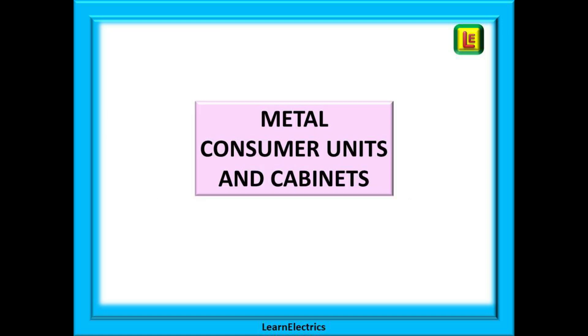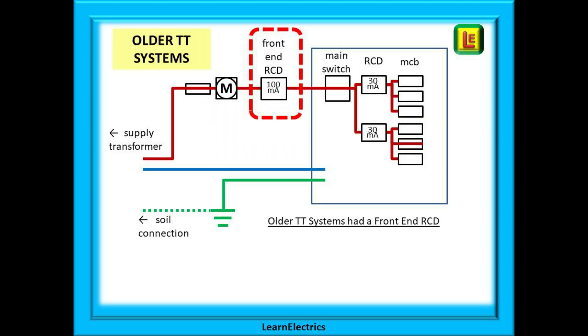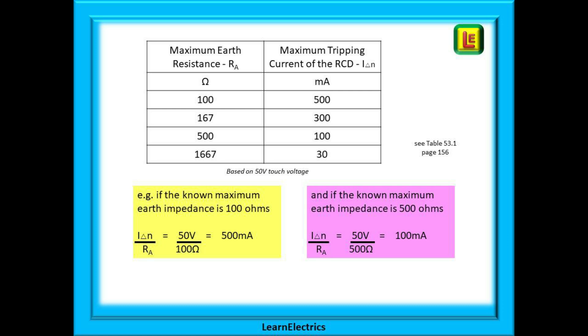Let's talk about metal consumer units and metal electrical cabinets. Older TT systems often used a front-end RCD — in other words, even if RCDs were fitted inside the consumer unit, a separate RCD was installed just before the consumer unit. This would often be a 100 milliamp delay type, or S type RCD, to allow for discrimination between devices. But why 100 milliamps — would another value ever be used? We have a table for this and the full version can be found in the wiring regulations book on page 156.